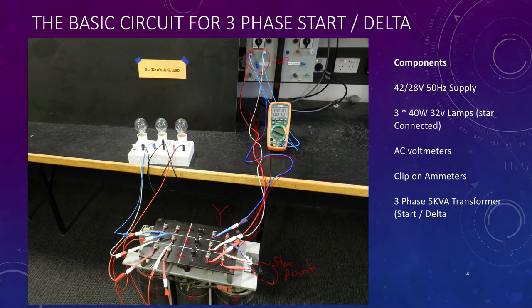On the secondary side, you can see that the end of the A phase has been looped around and connected to the finish on the B phase. And then the B phase finish looped around on the C phase. And then the C phase here looped all the way back around and onto the A phase. So at this end we end up with a delta connection.